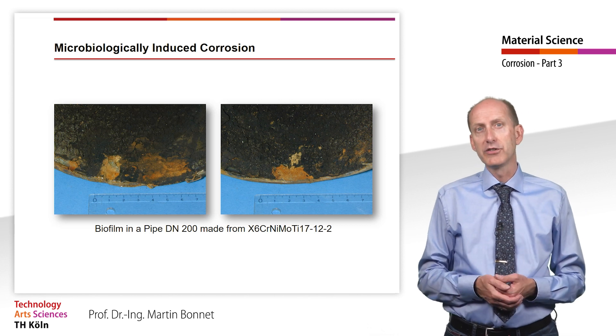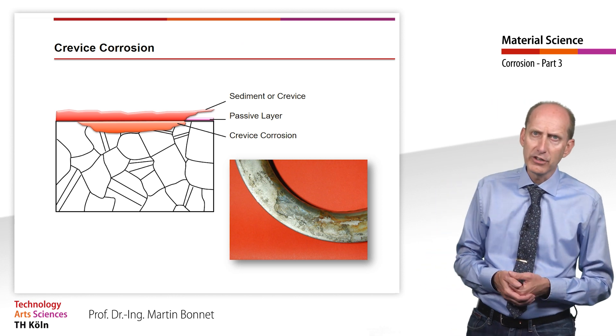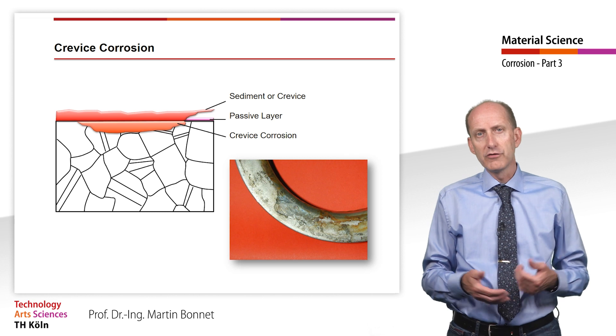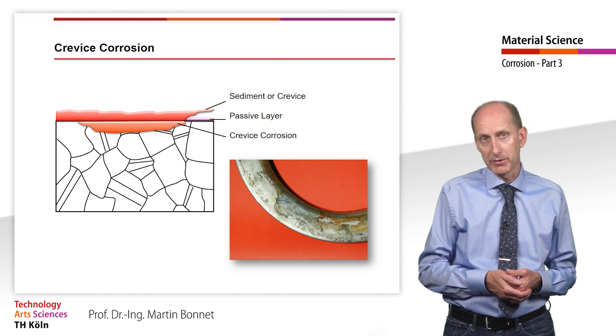Due to the geometric conditions created by the biofilm, crevice corrosion also occurred on the welding neck flanges in the case described above.